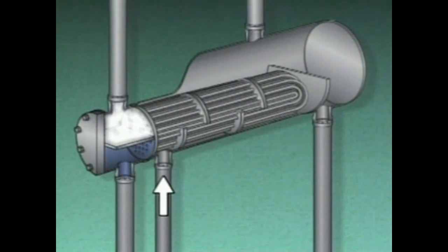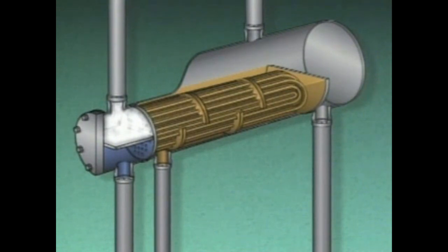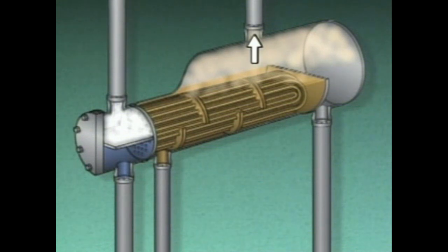Part of the liquid from the bottom of the distillation tower flows into the shell. A weir ensures that the tubes in the reboiler are kept covered with liquid. The vapors collect in the domed space in the shell and are then returned to the tower. Any liquid that is not vaporized is bottoms product that is sent on for further processing or storage.